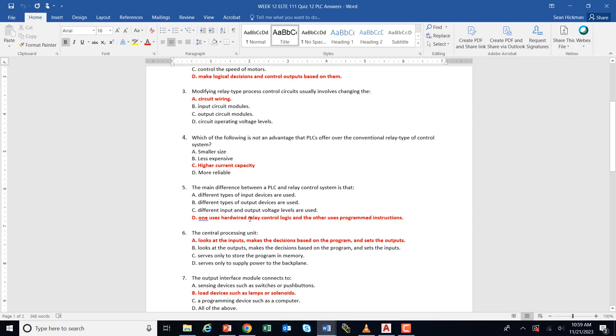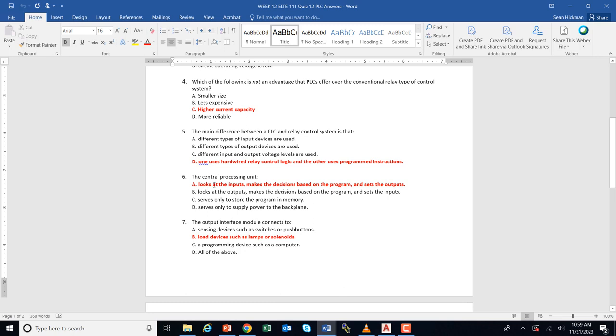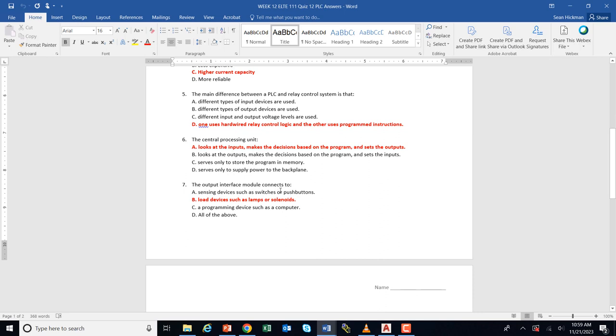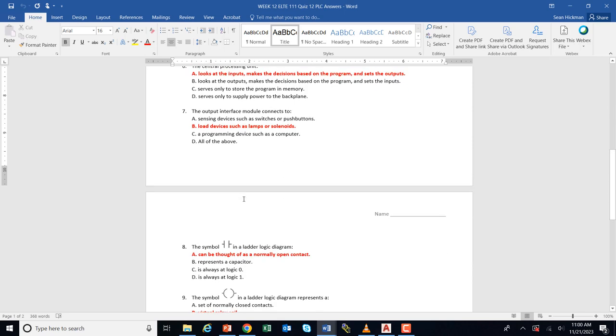The central processing unit looks at the inputs, solves your ladder logic program, and then sets the outputs. Check the inputs, solve the logic, update the outputs — that's what it does. The output interface module connects to the output, and that's your work: you hook your loads into it — lamps, solenoids, motor starters, stuff like that.